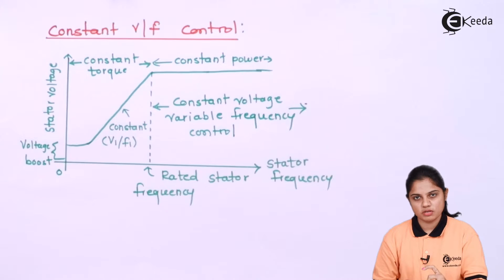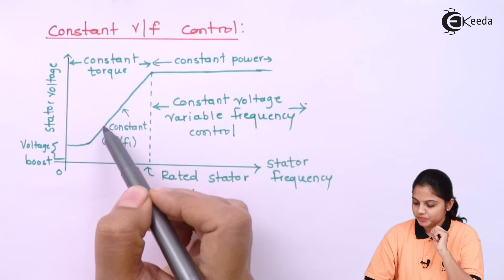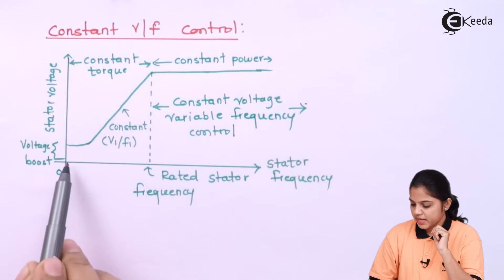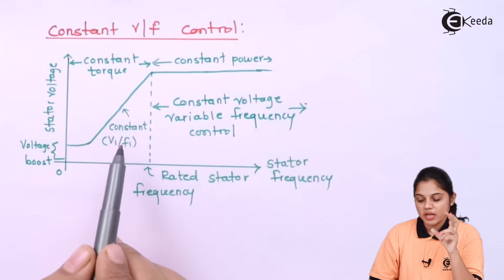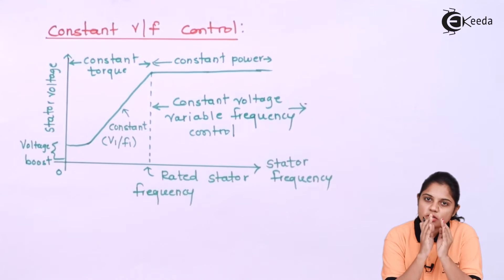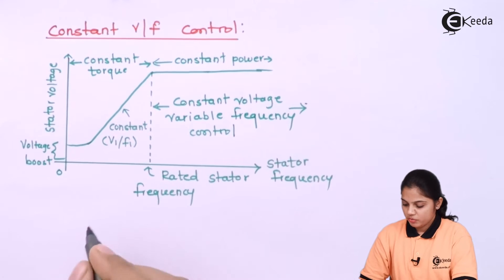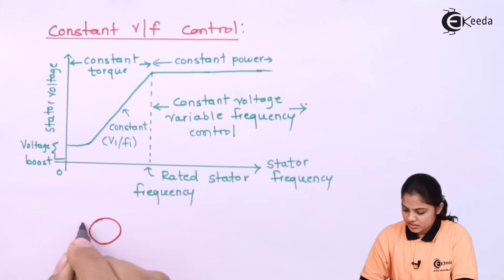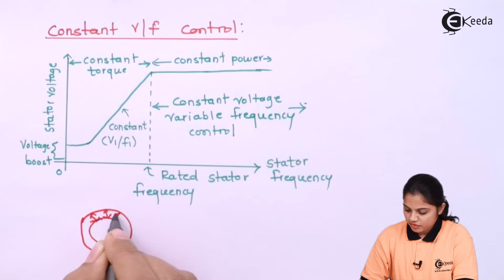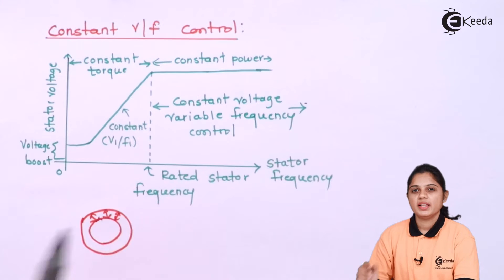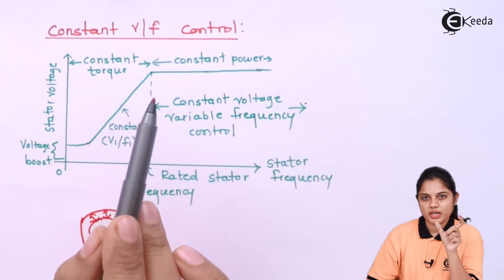You are changing the voltage and changing the frequency, but maintaining their ratio as constant. For that constant ratio, there is an increase in stator voltage and stator frequency. Because the ratio is constant, the air gap flux between the stator and rotor will remain constant, and therefore your torque will also remain constant for that particular period.